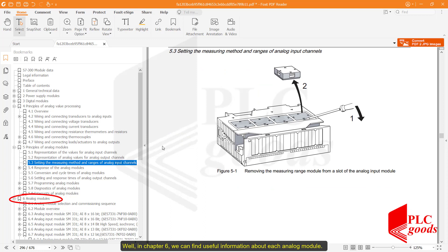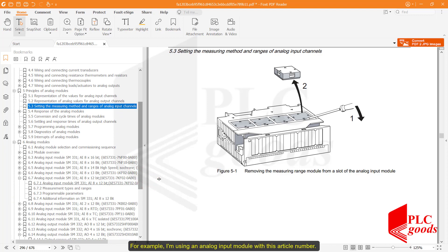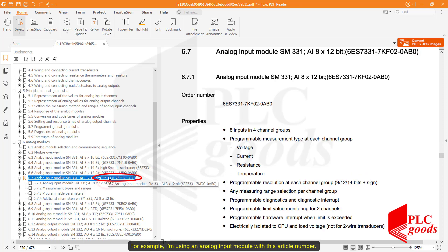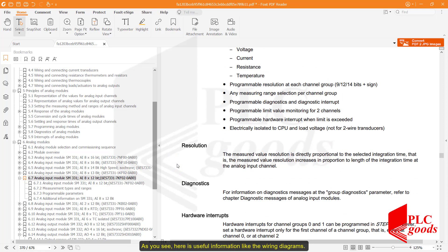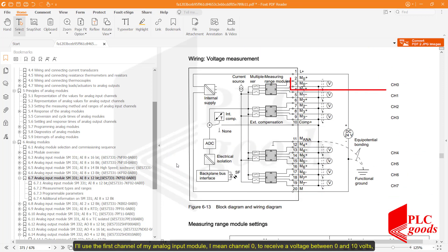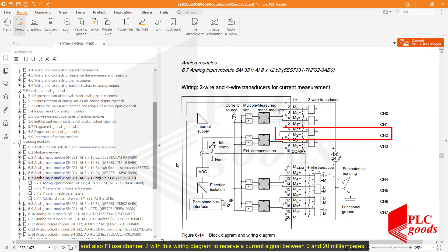In chapter 6 we can find useful information about each analog module. For example, I'm using an analog input module with this article number; here you can see useful information like the wiring diagrams. I'll use channel 0 of my analog input module to receive a voltage between 0 and 10 volts, and I'll use channel 2 with the corresponding wiring diagram to receive a current signal between 0 and 20 milliamps.